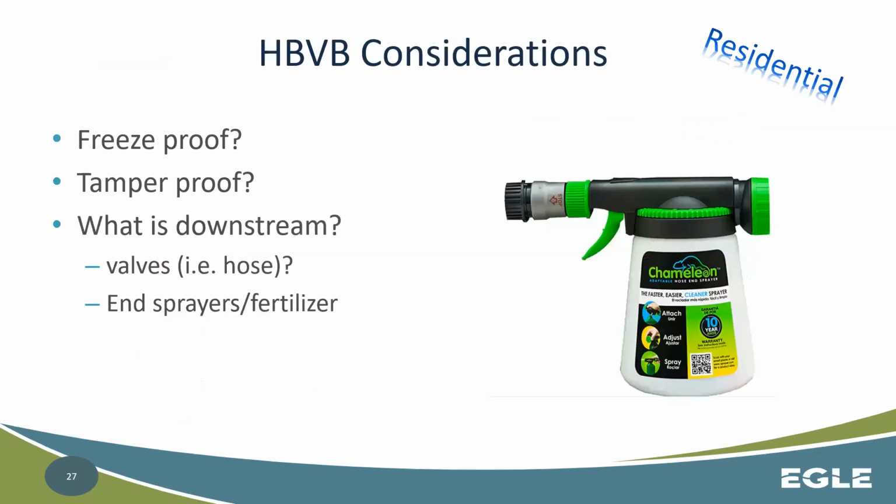One of the things to consider for some of the places where they've got the vacuum breaker is that sometimes it's not just as simple as I put something on it, and it's over with. You want to make sure, do you have a potential freezing concern that could damage that vacuum breaker? Are we going to have tampering concerns? Sometimes you might come back to a place and find that the vacuum breaker that was put on there might now have been removed.